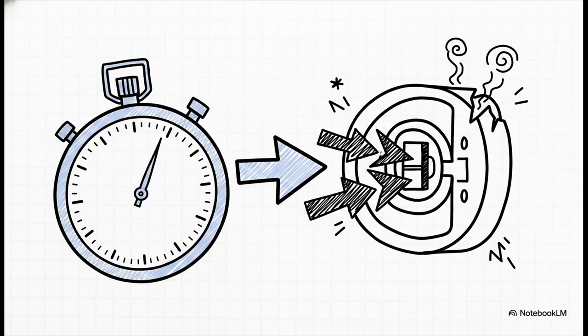Think about human nature for a second. When the power flickers or someone accidentally bumps the thermostat to off in the middle of a heat wave, our immediate panicked reaction is to flip it back to cool instantly. But when you shut a system off, the refrigerant pressures inside the lines are highly unbalanced. If you get impatient and restart it immediately, you're forcing the system's compressor to try and start up against that incredibly high pressure wall. You risk immediately burning out the motor. So if the system clicks off, take a breath, set a timer on your phone, and let 3 minutes of patience save your compressor from an early, very expensive grave.